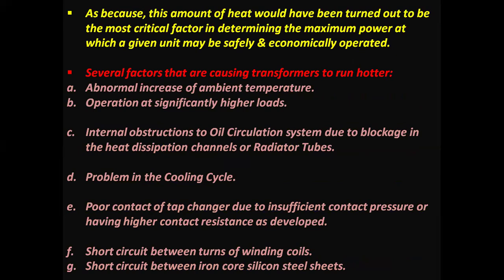There are several factors that cause transformers to run hotter. A. Abnormal increase of ambient temperature. B. Operation at significantly higher loads. C. Internal obstructions to oil circulation system due to blockage in the heat dissipation channels or radiator tubes, a problem in the cooling cycle. Poor contact of tap changer due to insufficient contact pressure or higher contact resistance having developed. Short circuit between turns of winding coils. Short circuit between iron core silicon steel sheets, that is, laminated sheets.